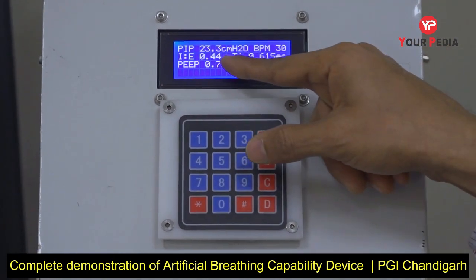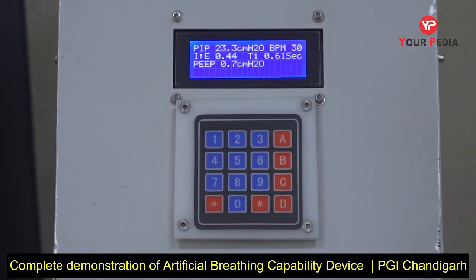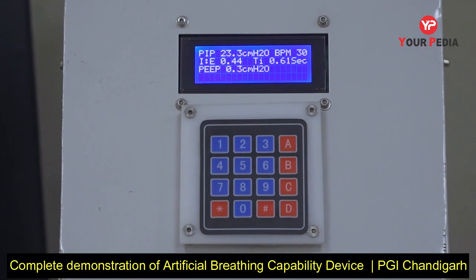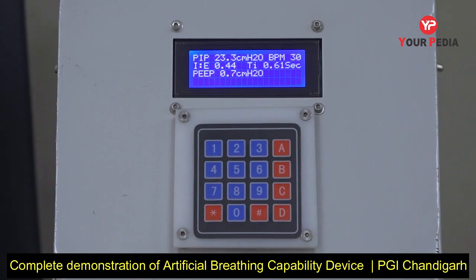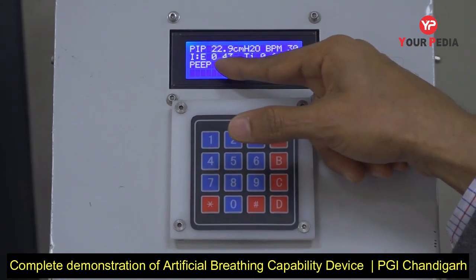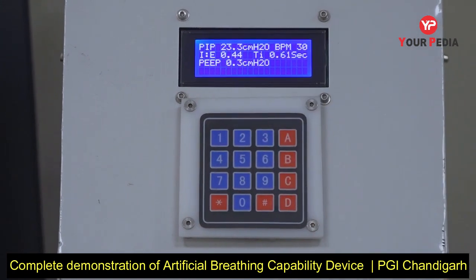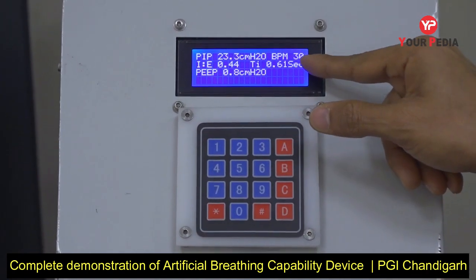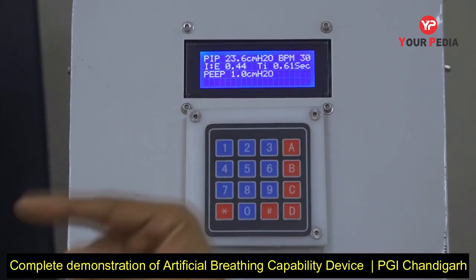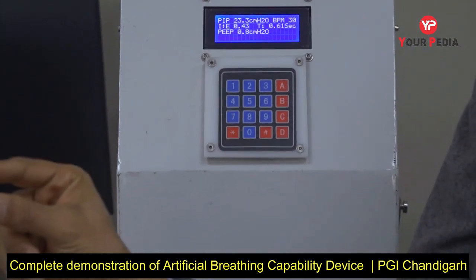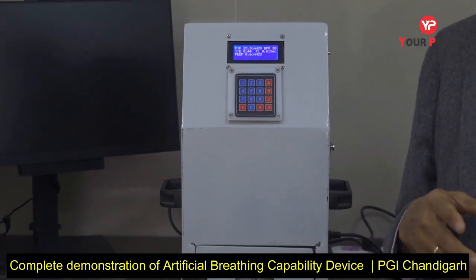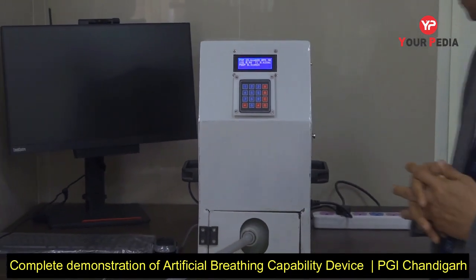The inspiratory to expiratory time ratio was set at 1:2.5, which in terms of decimals is 0.40. And you can see that this machine is varying between 0.43 to 0.44. And the inspiratory time is exactly as we set. The PEEP here we have not set, because the PEEP can be set through an automated valve through any number that we desire between 5 and 20 centimeters of water.